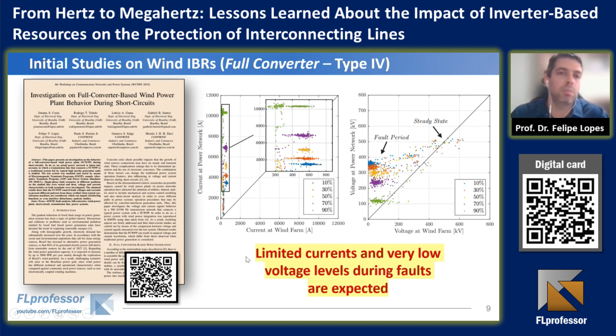And a very similar behavior in voltage was noticed, but this behavior was a little bit easier to follow, because there is a slight variation here in the voltage levels measured at the wind farm terminal when the fault position was changed. And the same thing was verified on the power network side. However, the voltages here are much smaller than those verified at the power network side. So we concluded that limited currents and very low voltage levels during faults are expected in this type of system. It was another learning.